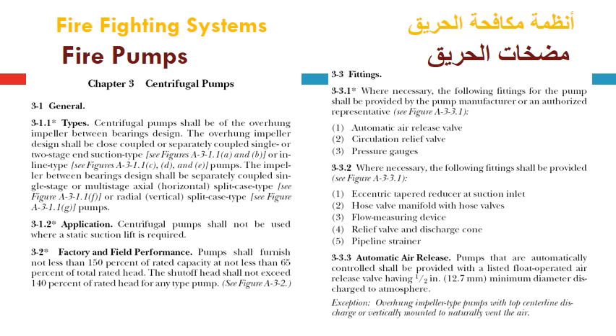Also, a relief valve should be provided between the non-return valve and the discharge flange of the pump to protect the pump from any expected maximum pressure that may happen in this short length. 5. Pipeline strainer, which is recommended in some cases to be added on the suction side to ensure the water purity in the suction line. Automatic air release: pumps that are automatically controlled shall be provided with a listed float operated air release valve having a half-inch minimum diameter, discharged to the atmosphere, to prevent air pockets in the discharge line and the pump casing during the pumping operation.